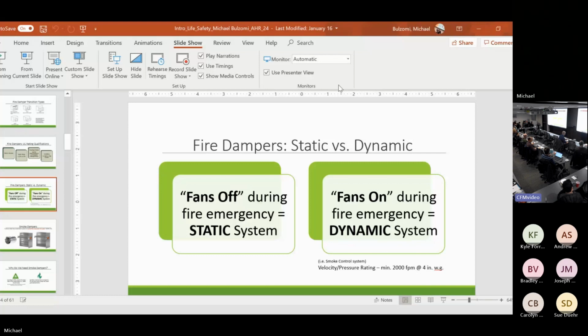Vertical on a wall, on a scale of dynamic testing, is pretty easy to pass. But horizontal in a ceiling is very difficult to pass dynamically in very large sections. So you can do a fire smoke damper almost 4 panels wide, 2 panels tall, 8 panels big, a really big damper vertically. Put that now in a dynamic situation and put it horizontally, and the listing becomes a lot less, because it's a lot more difficult to pass that test.